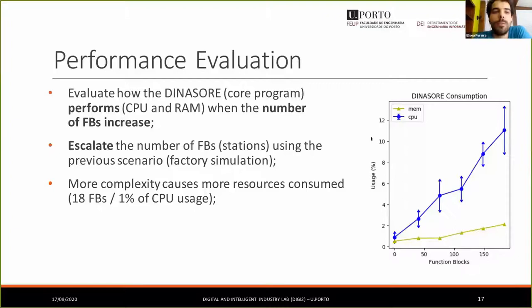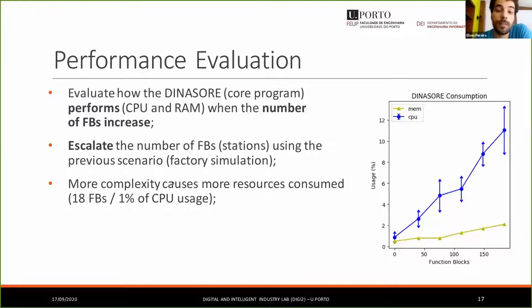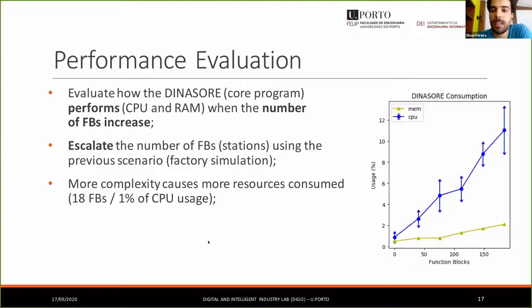We conclude that the complexity of more function blocks causes more resources to be consumed. The rate of increase is basically 18 function blocks per 1% of CPU usage. It is a scalable solution. If you have very high resource usage, you can also split the function blocks between two devices to avoid that higher consumption of resources.